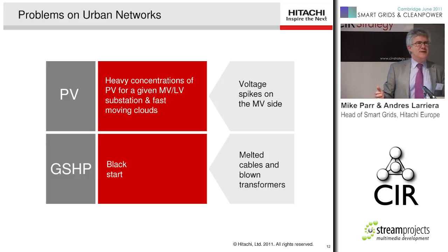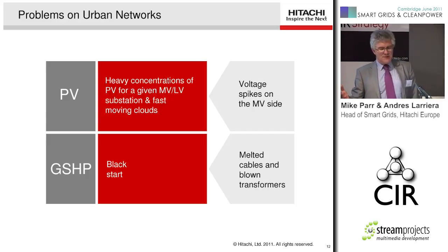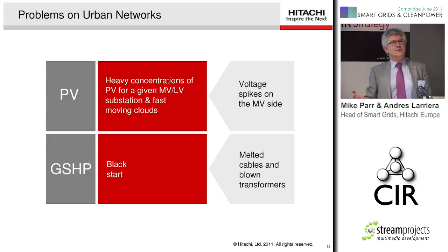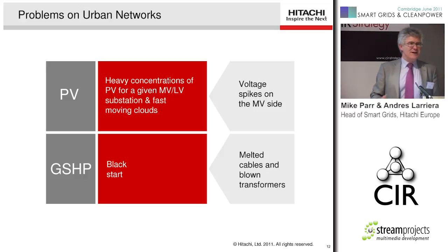The Dutch discovered this, and they've got a solution to it. Basically, imagine you've got say 100 houses, all with ground source heat pumps, and you lose power for 4 or 5 hours. This can happen - I was off for 8 hours last week because of a change in the substation where I live. But the point is, when the power comes back on, all those ground source heat pumps start at the same time. So it's then a bit of a toss-up whether your cable goes or your transformer blows up.